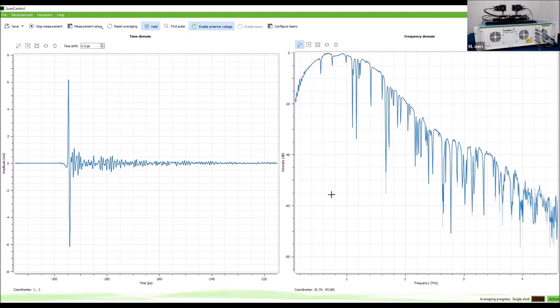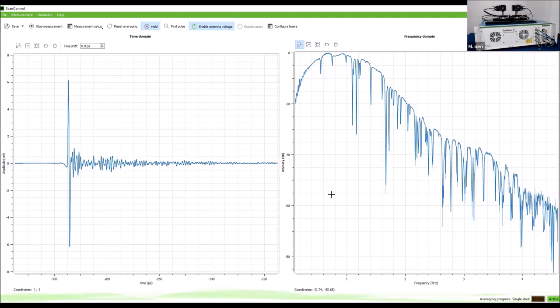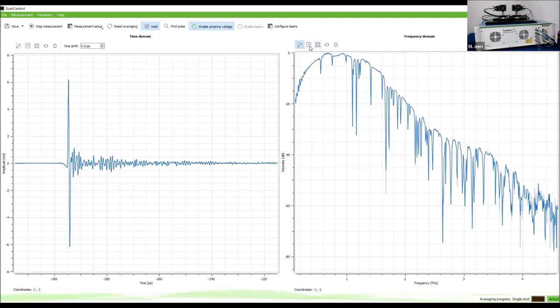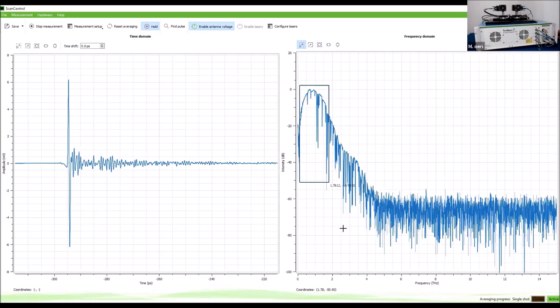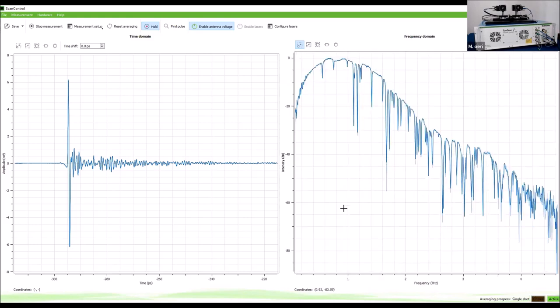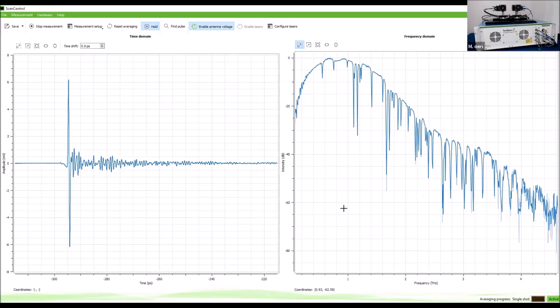These water absorption lines are actually a useful check: when we specify six terahertz bandwidth, we mean we can see spectroscopic features up to that point — mainly water lines. It is not only about noise level and signal level; it is also about a reproducible time axis. Water can disturb your experiment, but it can also be helpful to verify the instrument is performing as specified.